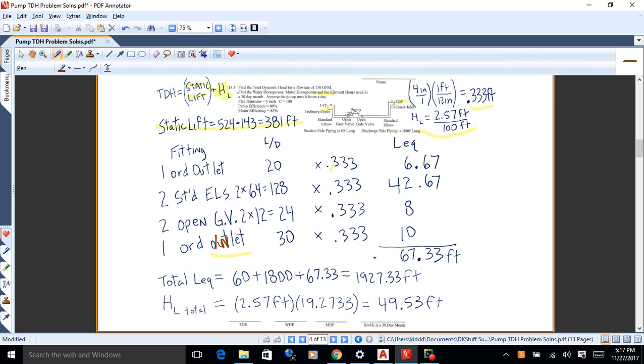So we look up the L over D values. That's the equivalent length over the diameter. You multiply that by the diameter in feet, which we found out was 0.333. So when we do that, we get these values over here. So that's the length of pipe you would run the water through to get the same head loss as the fittings. We want to get that total equivalent length. So we add up the column, we get 67.33 feet. So a 67.33 foot long piece of four inch pipe, C100, would have the same head loss as these fittings would. That's the idea.